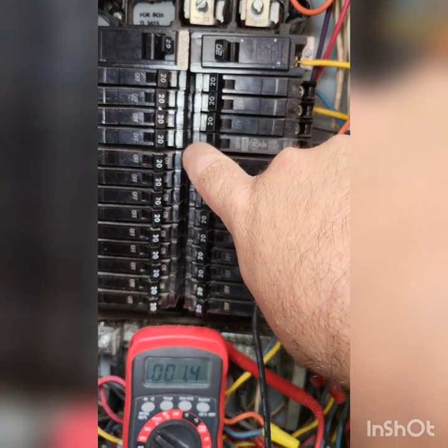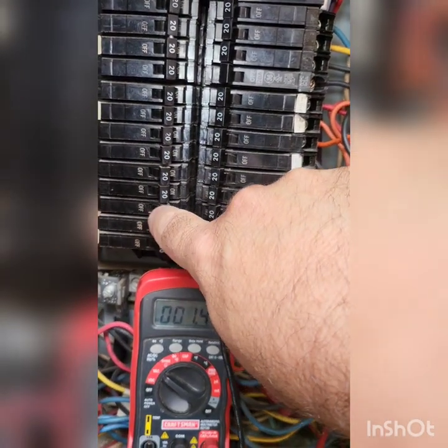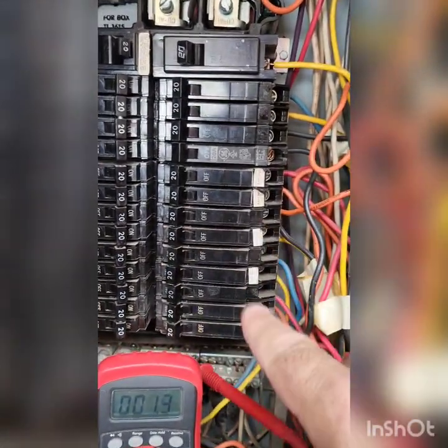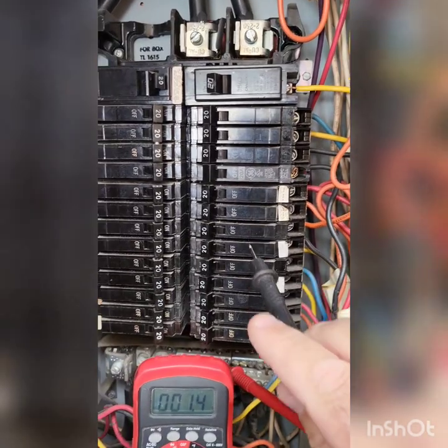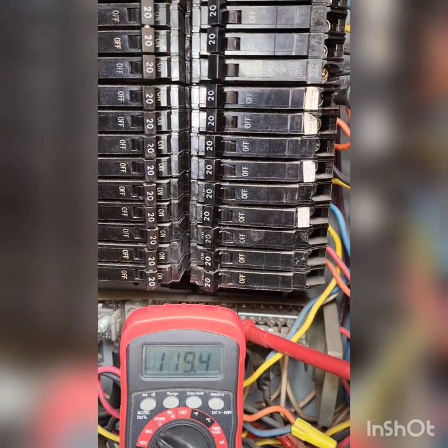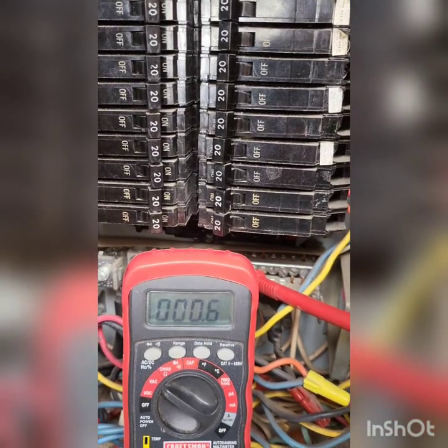I felt all the breakers coming down lightly because I don't know what else they control, and everything seems like they're on — just giving a little tug test to make sure. Now these are GE breakers, not Crouse-Hinds. If they were Crouse-Hinds you could have some other issues, but since they're a GE breaker in a GE panel, it's not normal for the breakers to be bad in these things. Let's take a look — coming down... good... uh-oh.